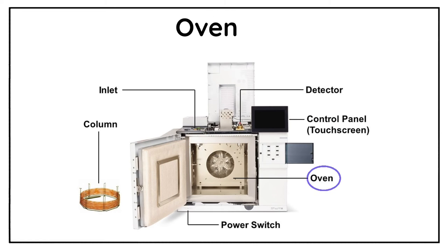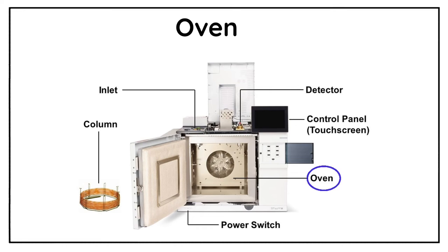Now comes the third part of the GC instrument, which is the column oven. This is how a typical GC column oven looks from the inside. The main function of the column oven is to provide high temperature as per analysis requirements. Generally the GC column is kept inside the oven, with one end of the column connected to the inlet and the other end connected to the detector.